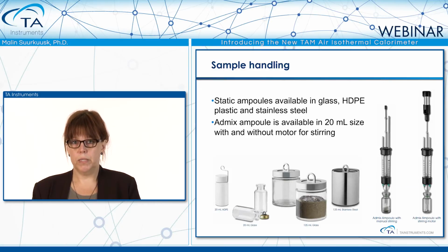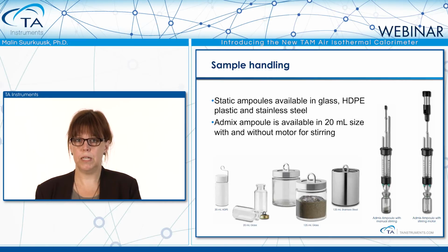And then you have the calorimeter, you have the thermostat, and then you need to put the sample into something, and that's what we call our sample handling system. We have static ampules, which means that we are not doing anything with the sample after we put it in the calorimeter. We put it in an ampule, put it into the calorimeter and measure what's going on. They are available in glass, plastic, and stainless steel, both for the 125 and for the 20 milliliter calorimeters.